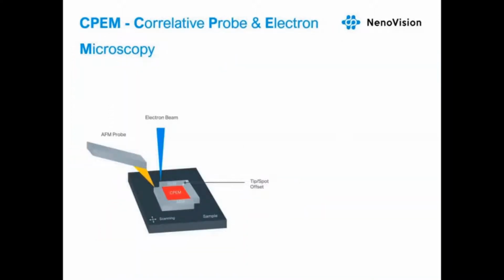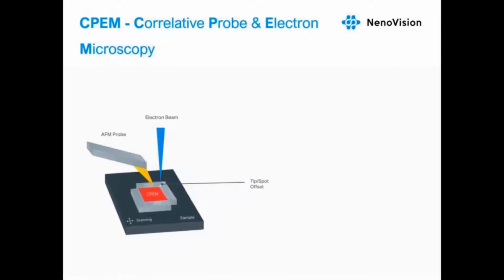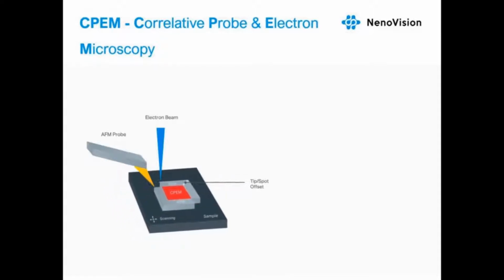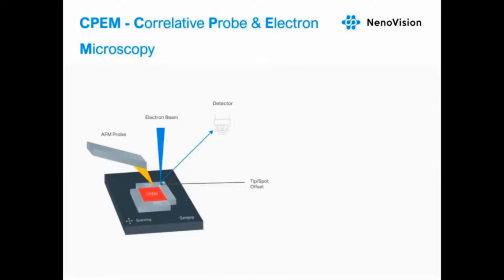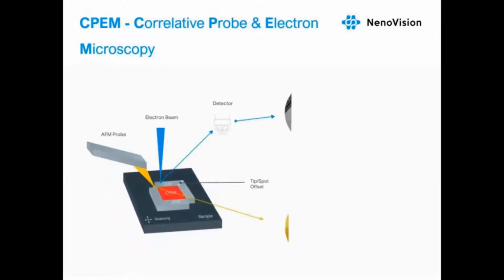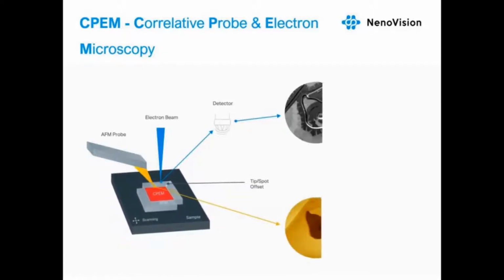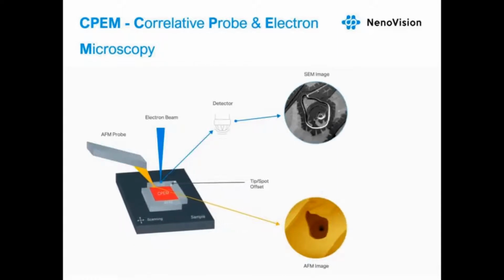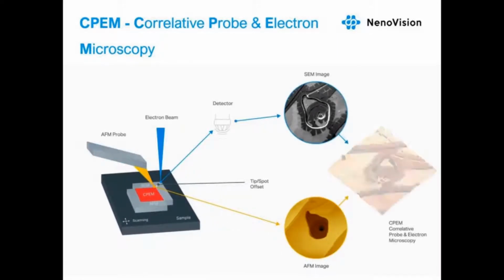And CPEM stands for correlative probe and electron microscopy, and it represents next step in correlative imaging. So let's have a look on how it actually works. So on the sample, the electron beam points close to the AFM tip with a constant offset. And during scanning, the AFM tip and electron beam remain static, and sample is being scanned only by the LiteScope piezo scanner, which enables simultaneous detection and acquisition of AFM and SEM signals at the same time, in the same place, and under the same conditions.